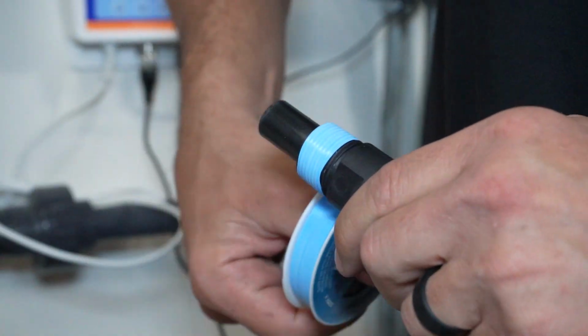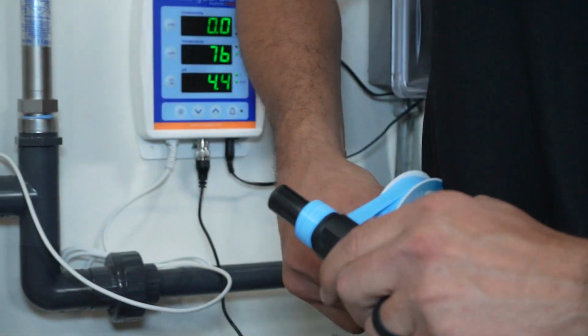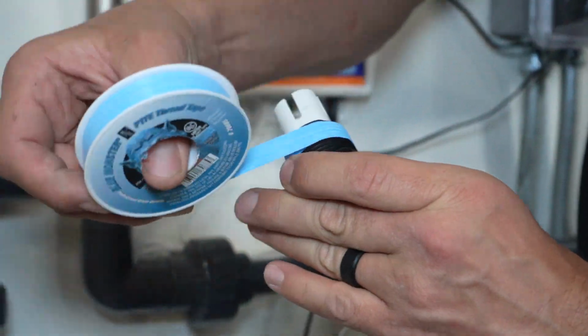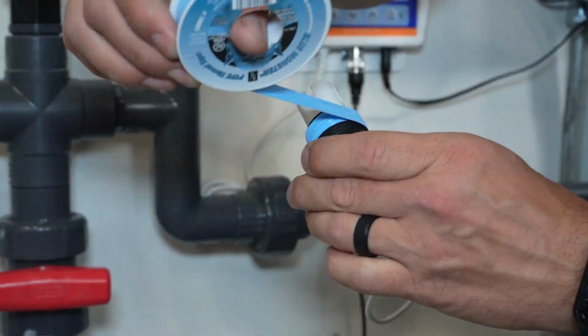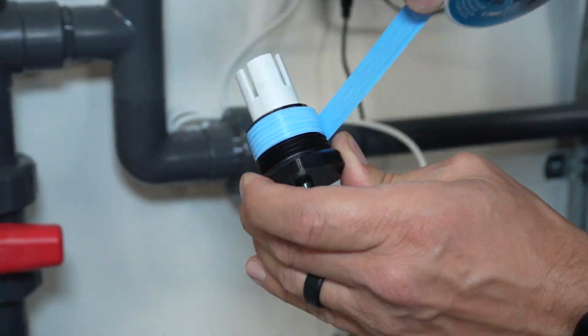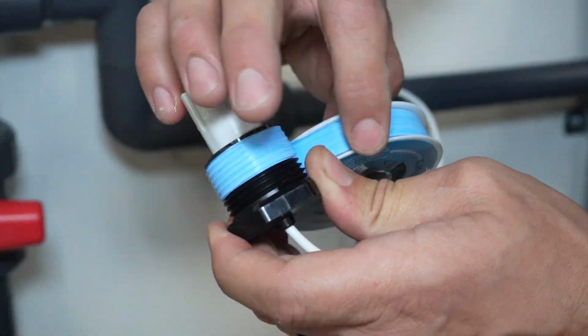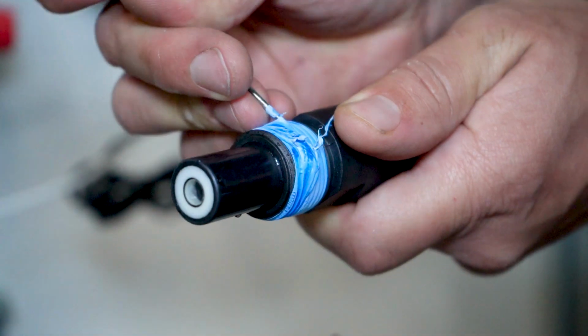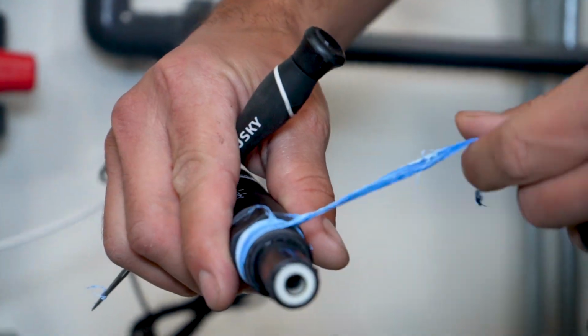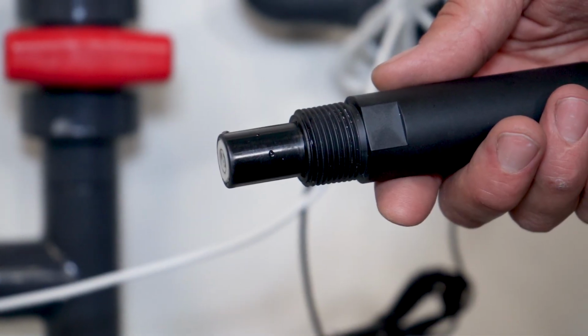Before installing the probes into the monitoring loop, wrap them with Teflon tape 5 full wraps in a clockwise direction. Do not over-tape the threads, as this will put excess stress on the PVC fitting and could result in a cracked fitting. When performing your 30-day calibration, remove all of the previously installed Teflon tape before retaping the probes. A pick or small wire brush is a helpful tool to remove the old tape.